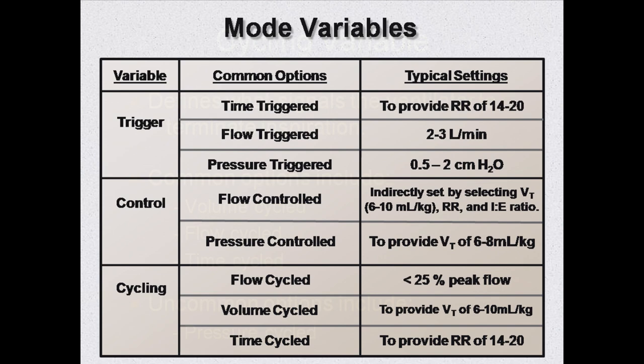Here is a summary of common options for the three mode variables. A mode can either be time triggered, flow triggered, or pressure triggered. It could be flow controlled or pressure controlled, and it could be flow cycled, volume cycled, or time cycled. Typical settings for these variables are listed to the right.